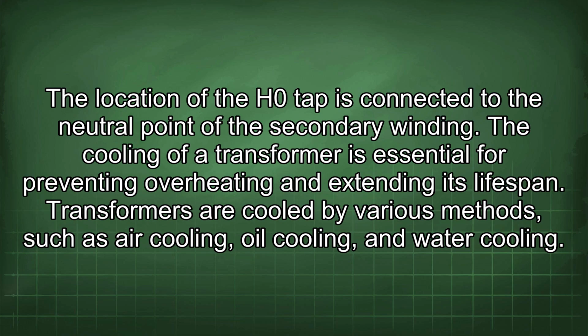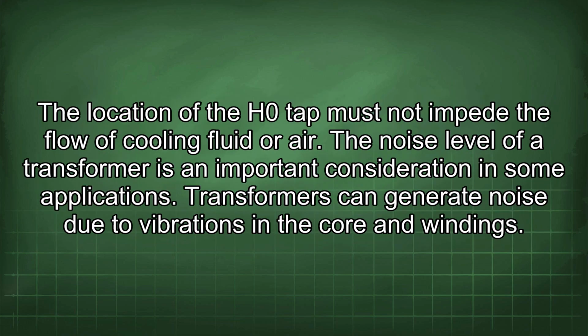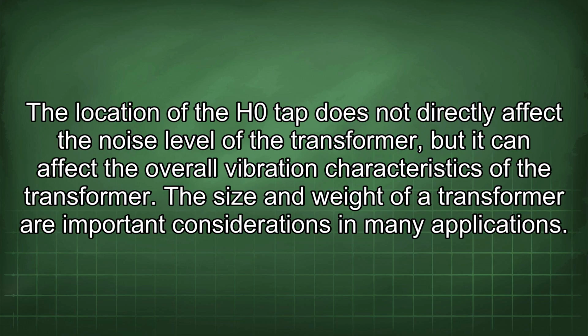The cooling of a transformer is essential for preventing overheating and extending its lifespan. Transformers are cooled by various methods, such as air cooling, oil cooling, and water cooling. The location of the H0 tap must not impede the flow of cooling fluid or air. The noise level of a transformer is an important consideration in some applications. Transformers can generate noise due to vibrations in the core and windings. The location of the H0 tap does not directly affect the noise level of the transformer, but it can affect the overall vibration characteristics of the transformer.